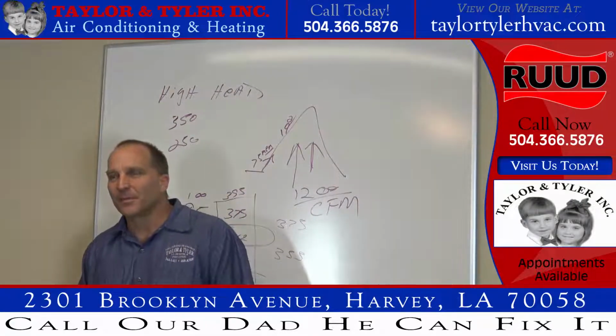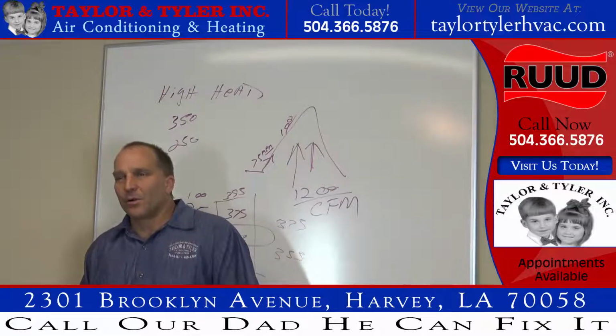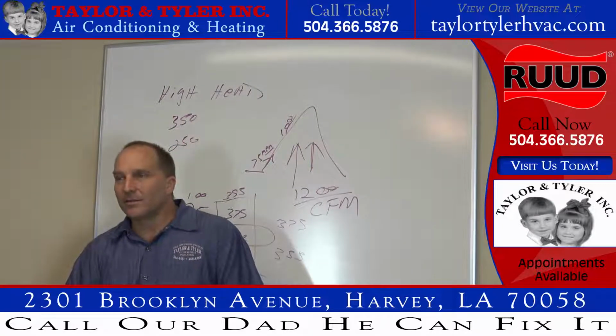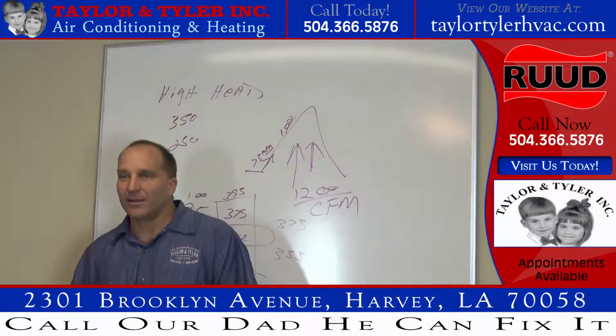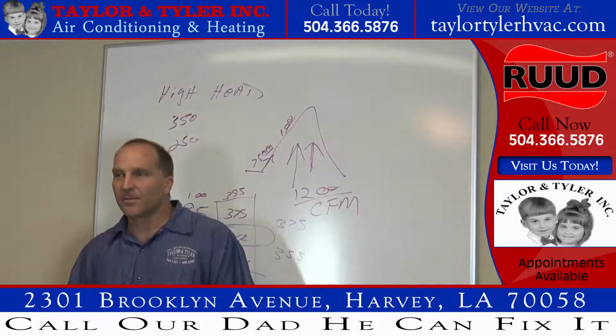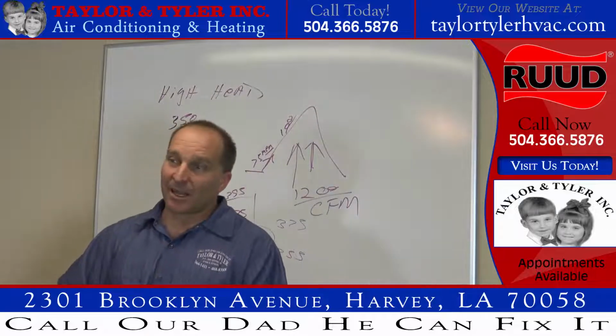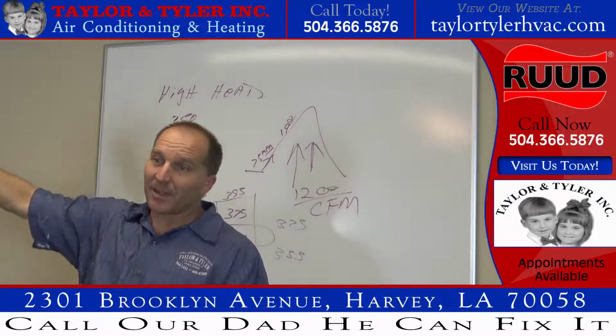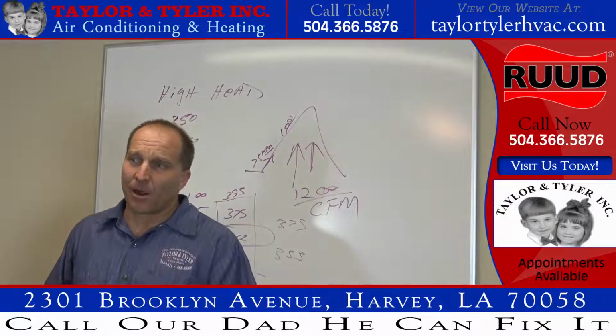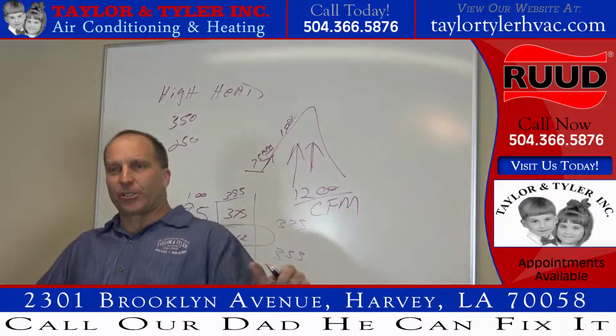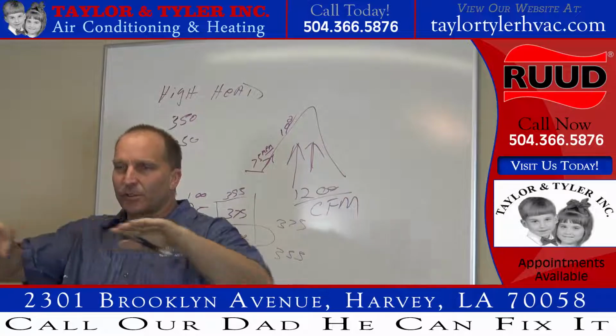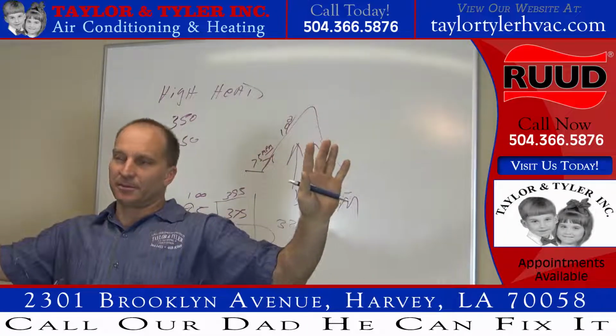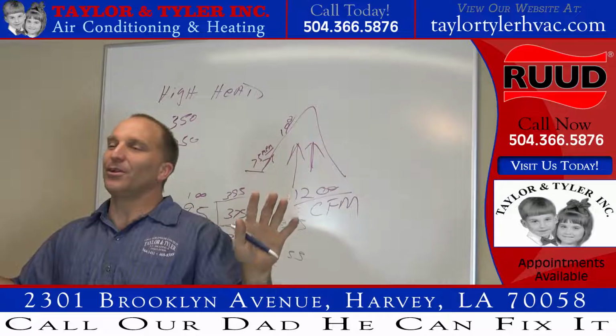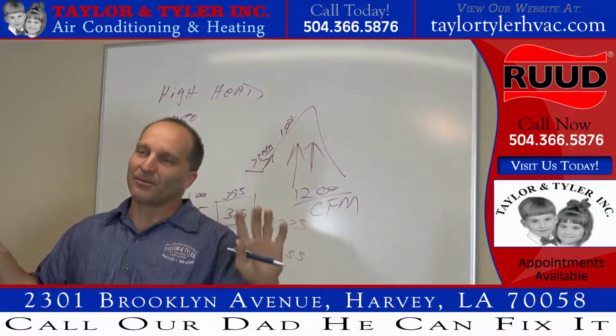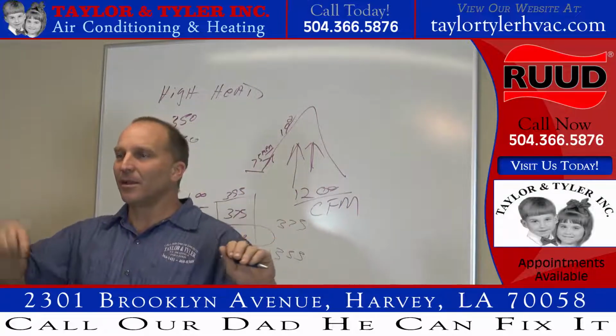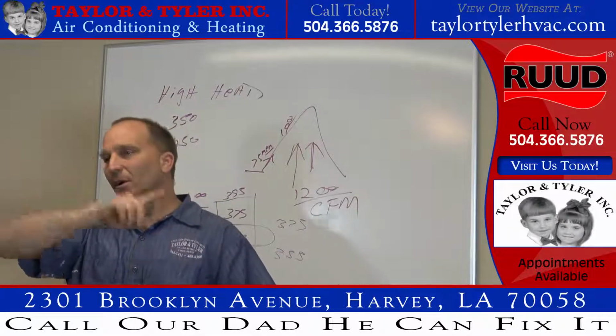Really weird. So I'm like, I don't know what is going on here. And then when I heard that noise, that triggered it. I said, okay, there's too much refrigerant in this system. And if you ever pump down a system that's got a really long line set, and as you're pumping it down, all of a sudden you hear that noise, and then your pressures equalize out. You didn't blow the unit up. Okay? You didn't blow the unit up. It's okay. All you have to do then is open your high side back again. Refrigerant will go back through the system and it'll start running again.